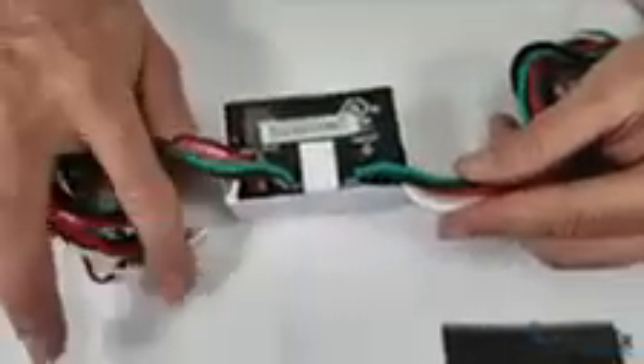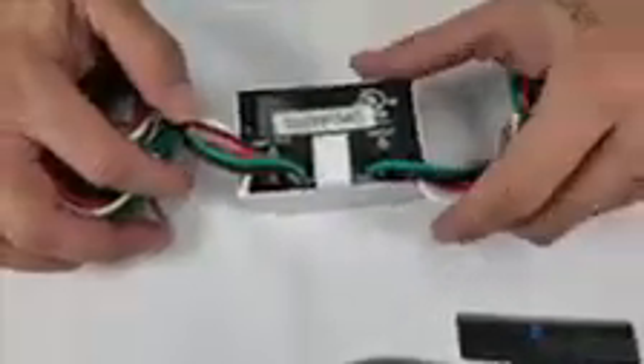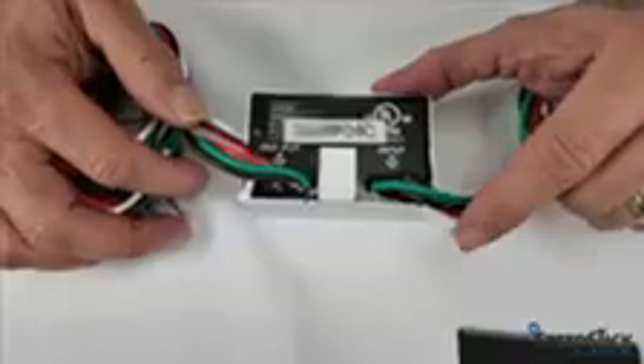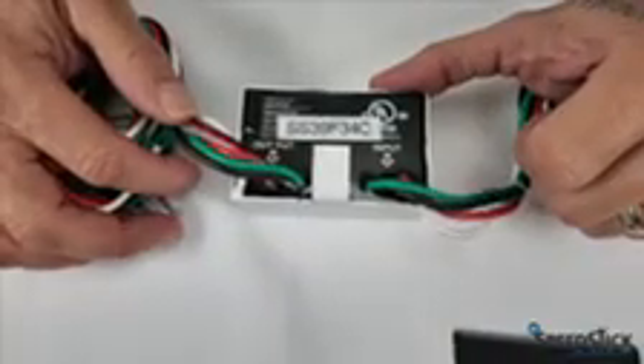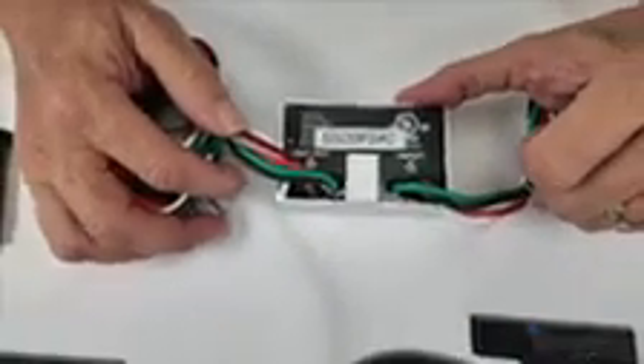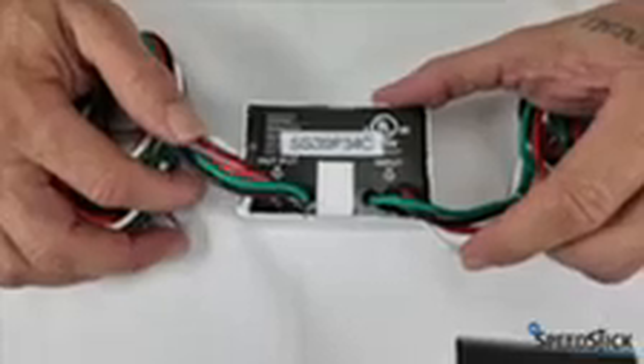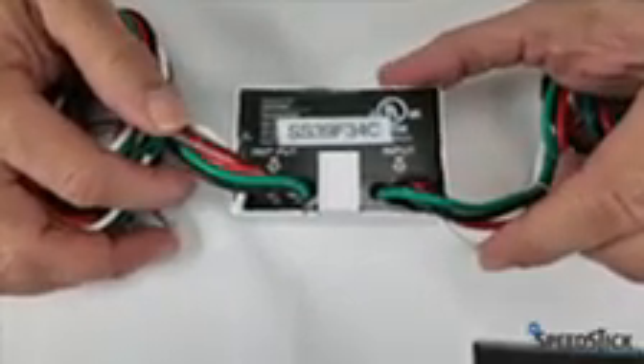Our white wire, when you're installing it, is the communication wire that runs through the module completely untouched. If you're working on Mitsubishis or Korean units, be careful and put your red to our white, because our white is communication. On Mitsubishis and Daikins and some of the Korean units, the communication wire is red.